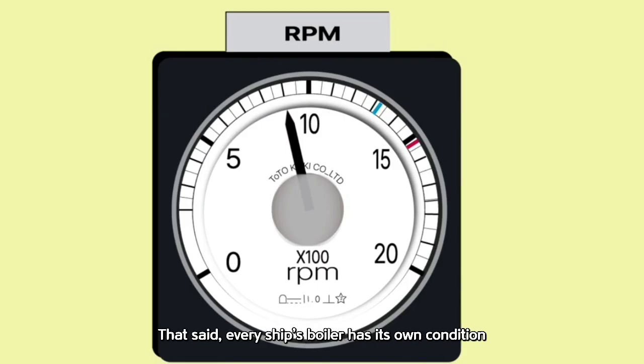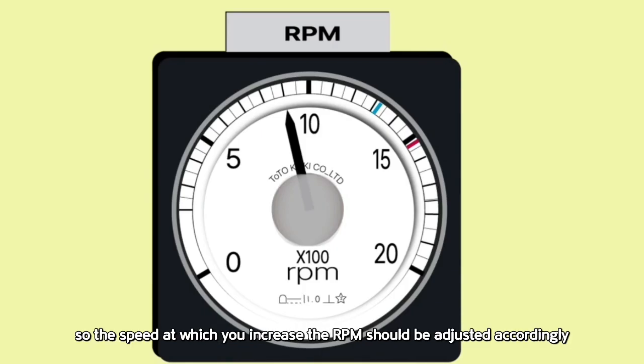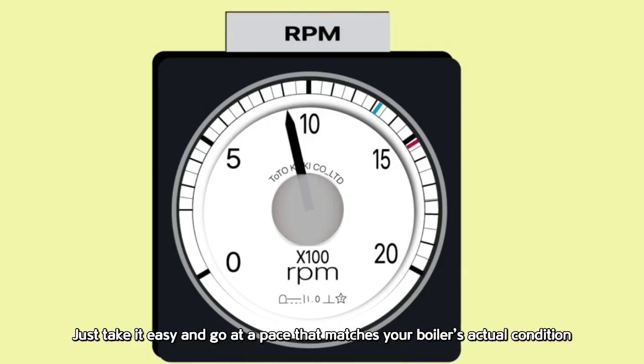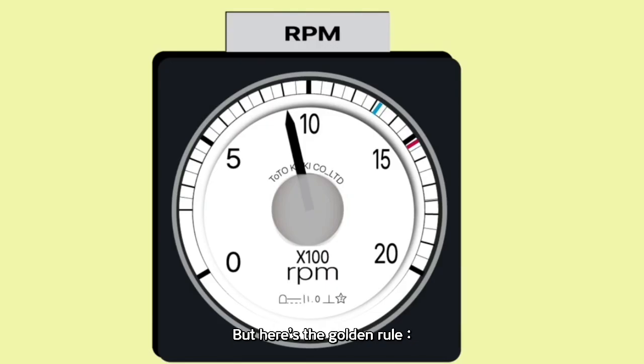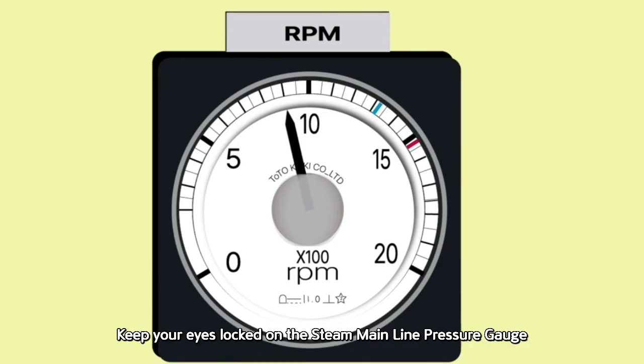That said, every ship's boiler has its own condition, so the speed at which you increase the RPM should be adjusted accordingly. Just take it easy and go at a pace that matches your boiler's actual condition. But here's the golden rule. Keep your eyes locked on the steam mainline pressure gauge or the exhaust pressure gauge, whichever one your ship has. Watch them closely as you bring the RPM up toward 900.